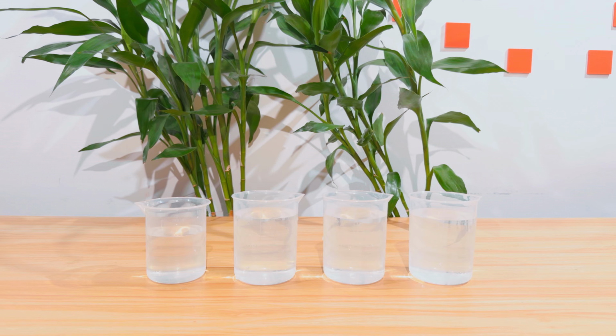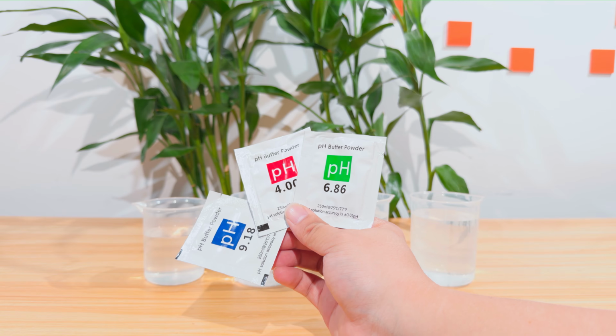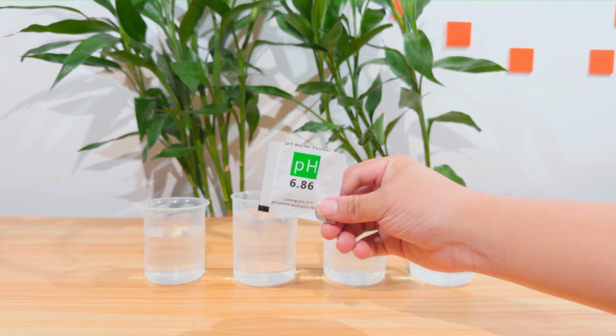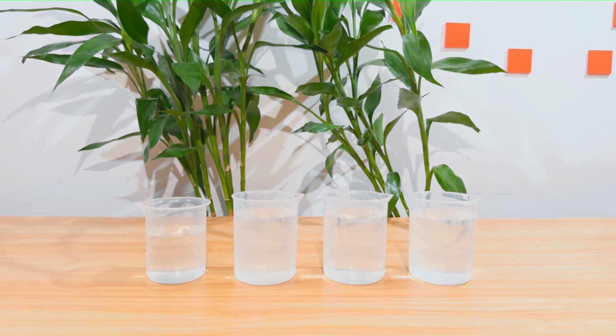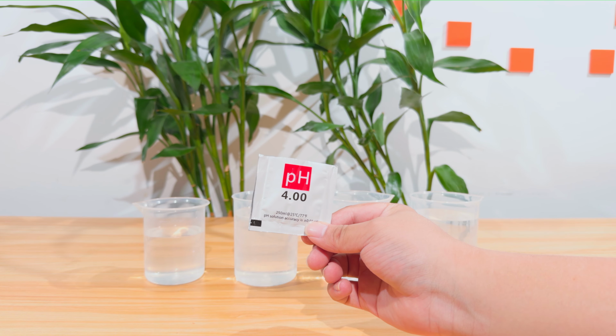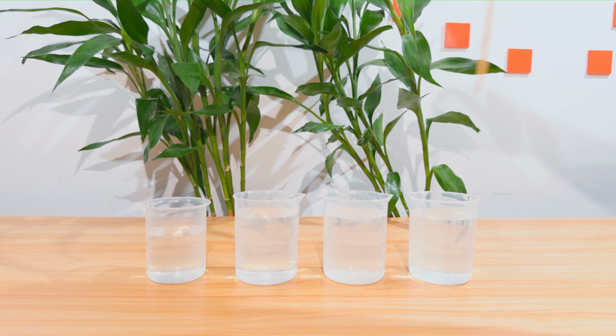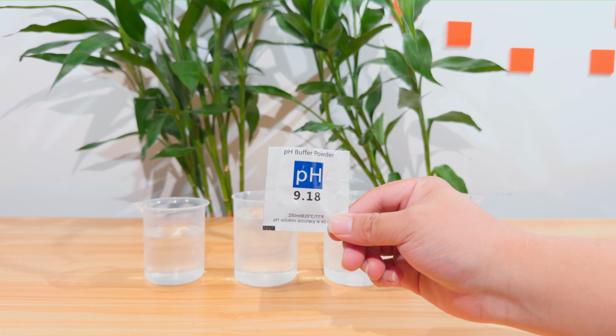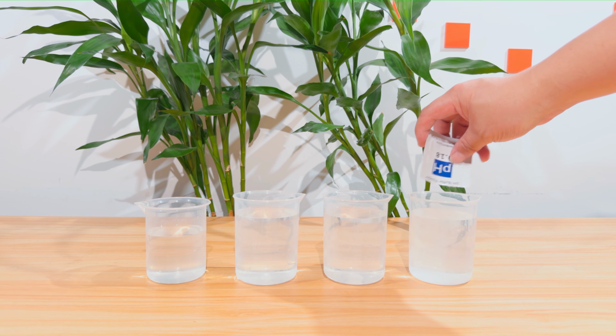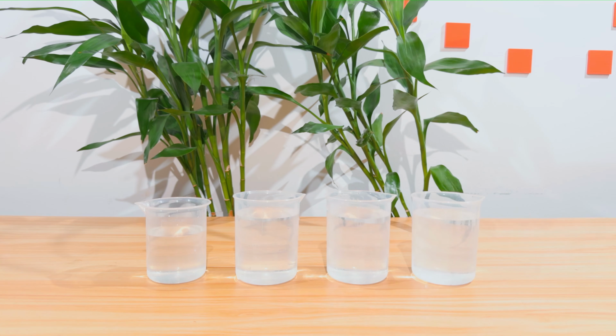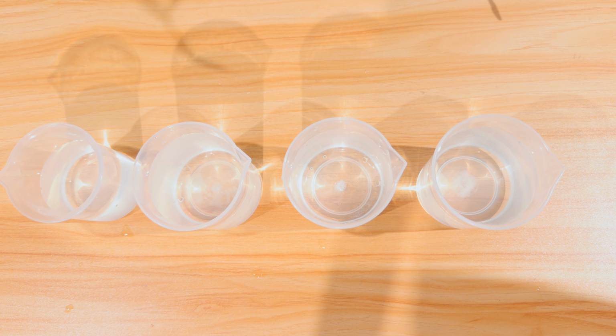When calibrating the pH probe, get ready 4 cups of 250 milliliters purified water and pH calibration powder first. First pour in the pH 6.86 calibration powder and dissolve it. Then pour in the pH 4.0 calibration powder and dissolve it. Finally pour in the pH 9.18 calibration powder and dissolve it. Leave the mixed solutions for 5 minutes until the powder dissolves almost completely.